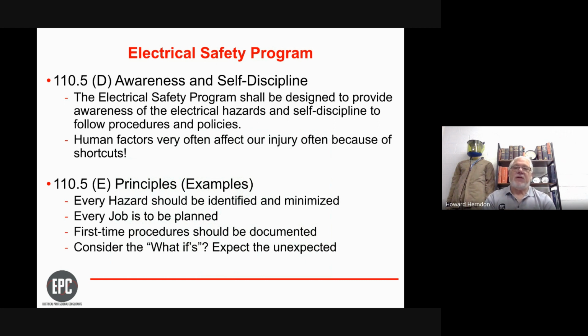We want to have the self-discipline for somebody to say, no, this equipment has to be de-energized to do this. And I think that's a big fallacy we have in the electrical industry and many other areas and arenas of construction, is also maintaining equipment, is that equipment can be shut down. We just have to find the right time. It may not be convenient to work on this piece of equipment at 2 a.m. on a Sunday morning, but maybe that's the time to do it. Maybe it's a casino and we have to work on it on a Tuesday night at 4 a.m. So there's many things that we can do. I have yet to find too many pieces of equipment that could never be shut down. And if there are, that's typically a design issue that has to be addressed.